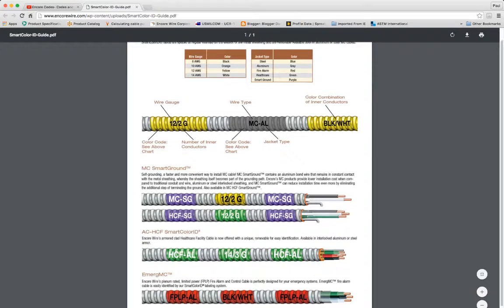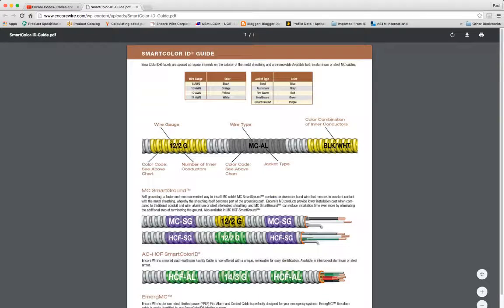If you look at the very top, you'll see that the guide gives you some basic information to help you understand. If it's an eight gauge conductor inside, it's going to have black labels. If it's a 10 gauge conductor inside, it's going to have an orange label, most notably over here where it talks about the wire gauge. When you see that it's a 12 gauge, it's going to have a yellow wrapper. If it's a 14 gauge, it's going to have a white wrapper. So immediately at a glance, I know exactly the size conductors that are in this cable.